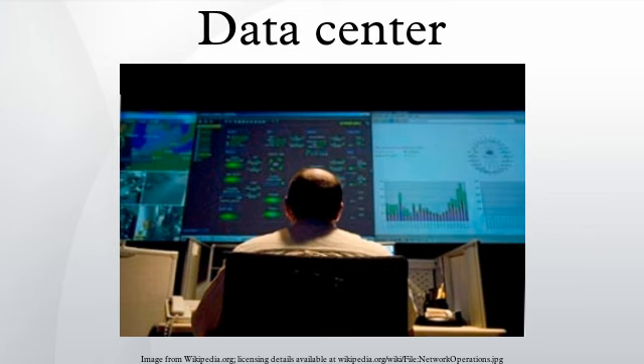A data center can occupy one room of a building, one or more floors, or an entire building. Most of the equipment is often in the form of servers mounted in 19-inch rack cabinets, which are usually placed in single rows forming corridors between them. This allows people access to the front and rear of each cabinet. Servers differ greatly in size from 1U servers to large freestanding storage silos which occupy many square feet of floor space. Some equipment such as mainframe computers and storage devices are often as big as the racks themselves, and are placed alongside them. Very large data centers may use shipping containers packed with 1,000 or more servers each. When repairs or upgrades are needed, whole containers are replaced.